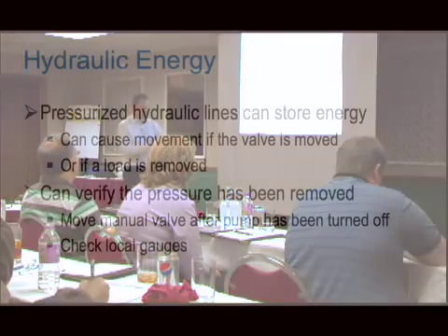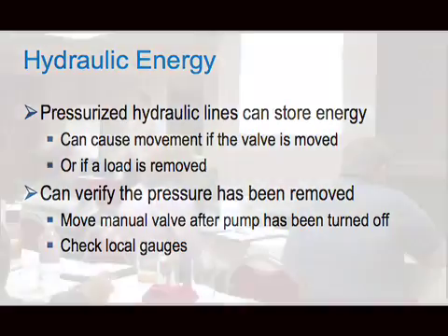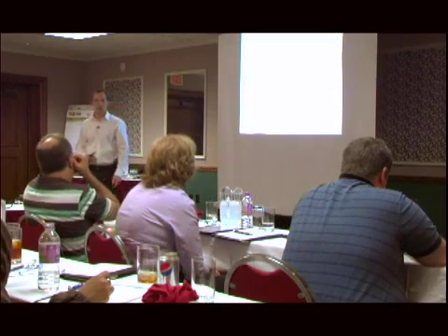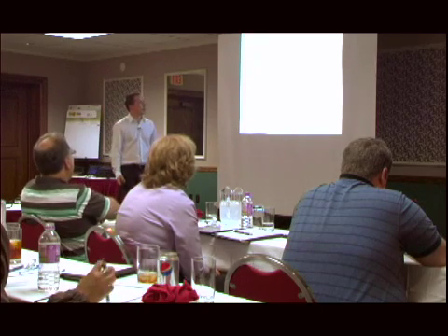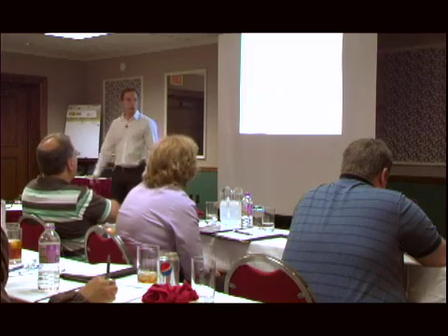Hydraulic energy. Pressurized hydraulic lines can store energy even after you have them locked out. It can cause movement if the valve's moved or if the load is removed. To verify the pressure's been removed, move the valves, check the gauges, use the machine to verify that before you work on it, that it's zero energy state. And those are just some of the non-lockable energies. There are others that are going to be in the facility.